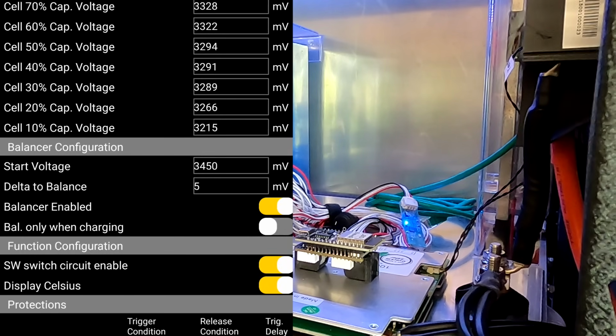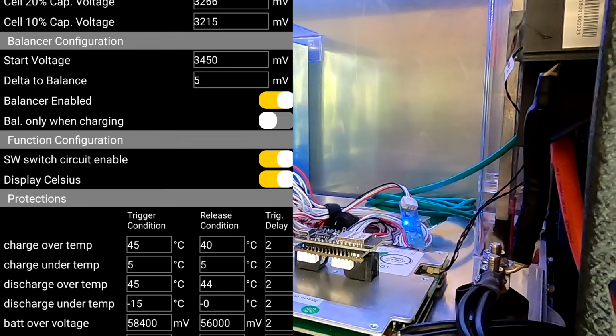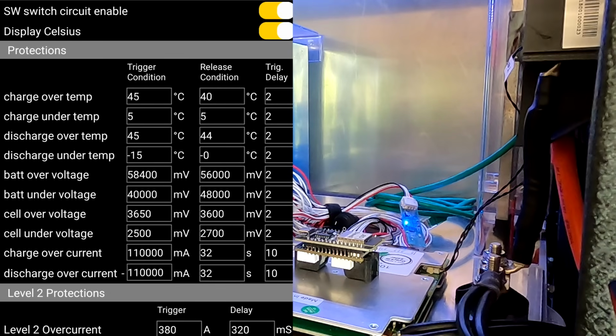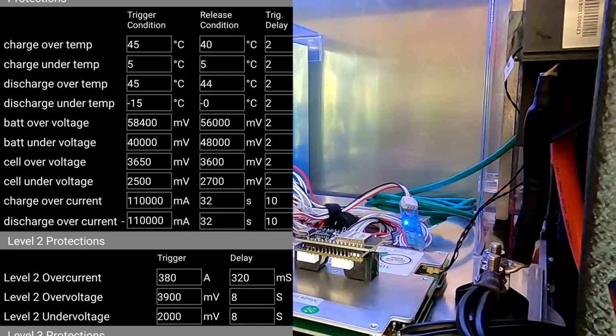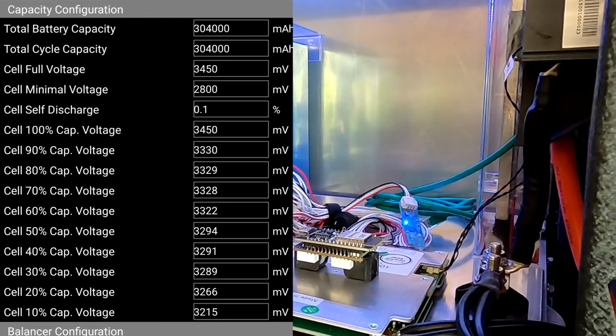Balance start voltage 3.45, delta 5 millivolts. Balance only when charging is off, so we are balancing when the battery is idle. Over voltage 3.65, under voltage 2.5, 110 amps charging and discharging, and this is the short circuit current, 380 amps. Okay, that is all good as far as I can see.